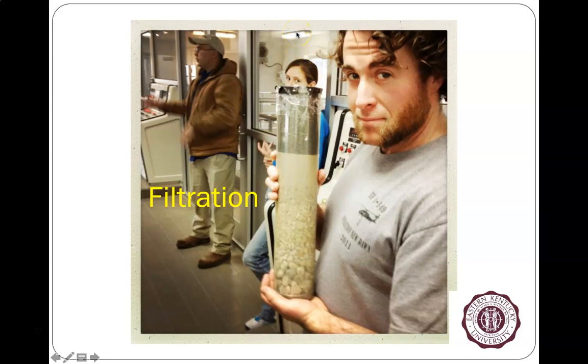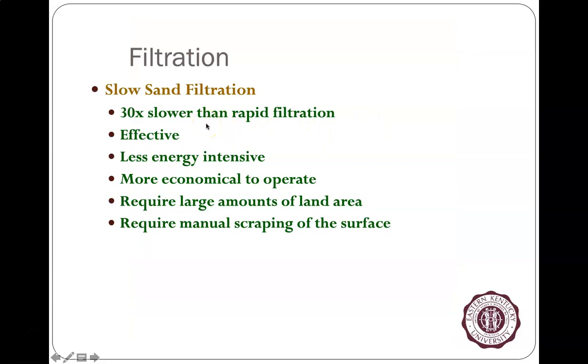If it takes more head pressure to push the water through, it means a lot of the pores are starting to get filled up. Once the head pressure gets too high, or turbidity rises above acceptable levels, they can take the filter offline and backwash it — pushing all the water out along with the sludge and muddy material. The water plant actually has an NPDES permit for that backwash water, which goes to sludge ponds where the sludge is removed before the remaining water is discharged under permit.